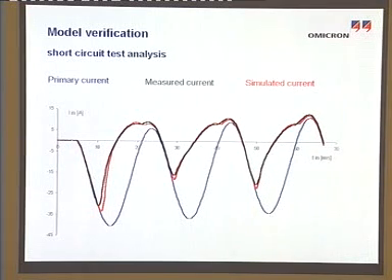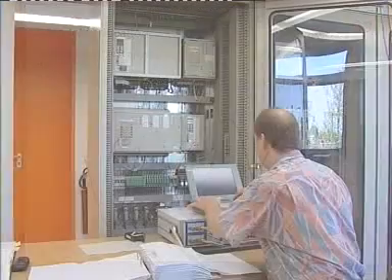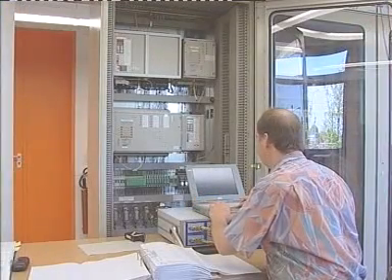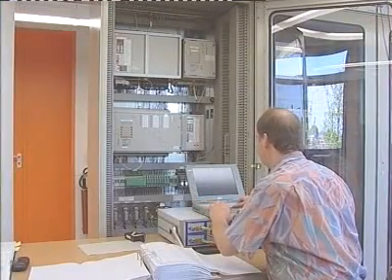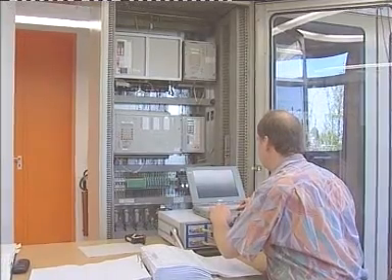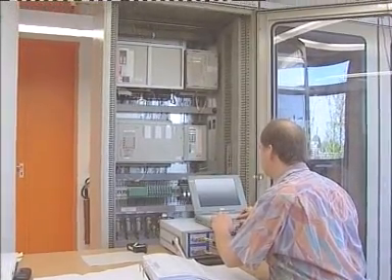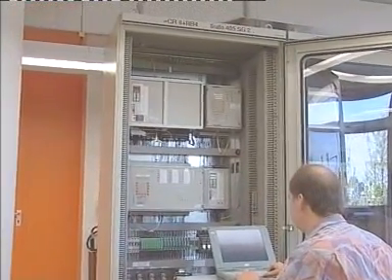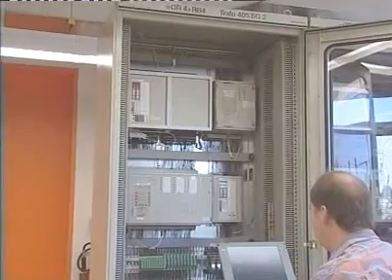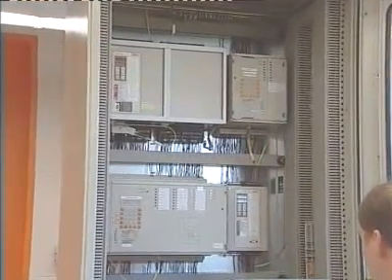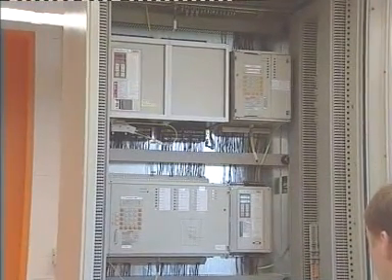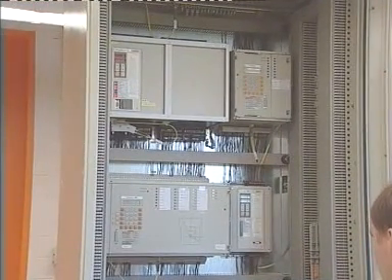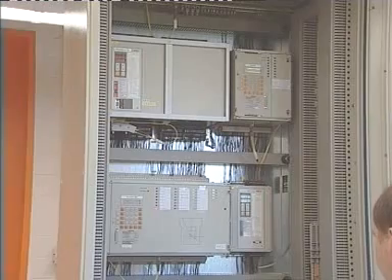Thus, the suitability of this model can be proven. Should the algorithms of the protection relays not be known sufficiently and therefore offline simulation cannot be performed, the test is effected with the theoretically calculated signals by means of the secondary test set CMC256 and by transient data output.